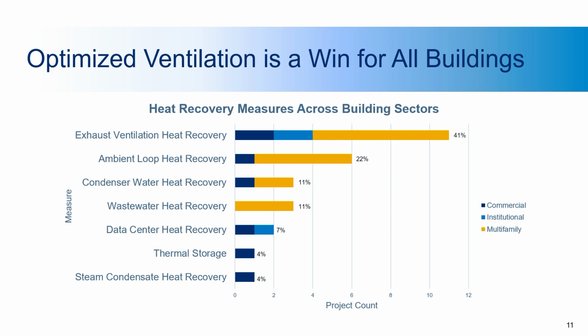They're color-coded by building type. You'll see heat recovery from ventilation, via an ambient loop, from condenser water, from wastewater, and also from data centers and steam condensate. We can also help fund thermal storage when paired with other heat recovery measures. One takeaway is that optimized ventilation is effective for all building types. We also found that multifamily buildings were way over-ventilated, meaning the exhaust was running too much, so there's a big opportunity for multifamily to right-size new heat recovery ventilation.